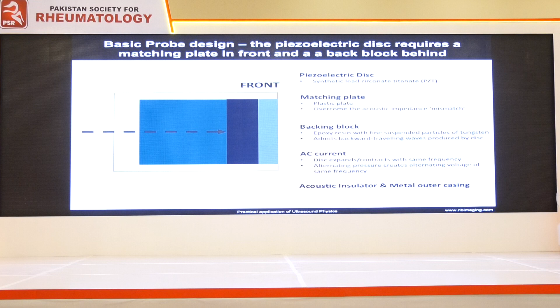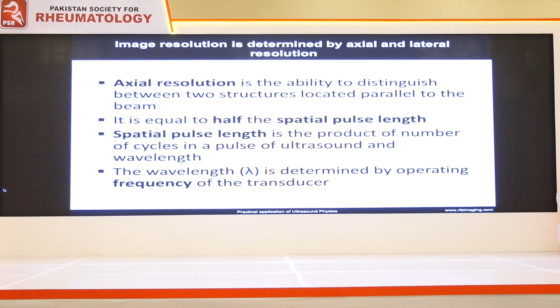So here are some very basic principles. I don't want to spend too long on this slide, but essentially, axial resolution is your ability to distinguish between two structures at different lengths that are parallel to the beam. It's related to the spatial pulse length, and the spatial pulse length is determined by the wavelength. And the wavelength is determined by the frequency of the transducer. We'll go through all of this in a moment, and it will become a bit clearer what all this stuff means. So here's the basic principle.